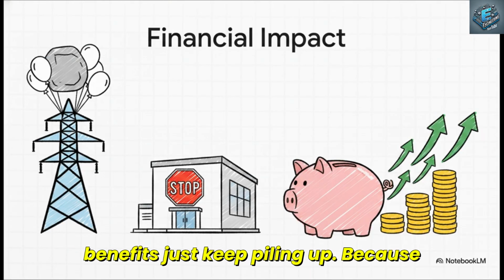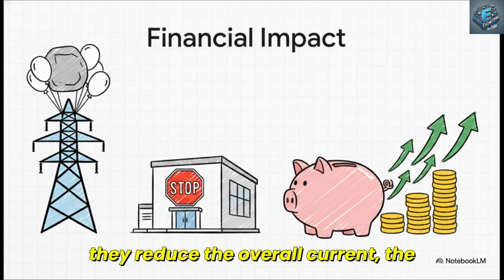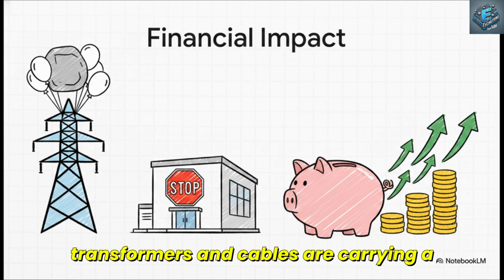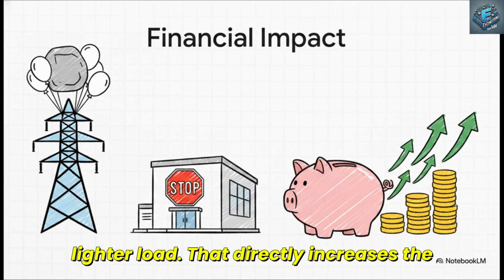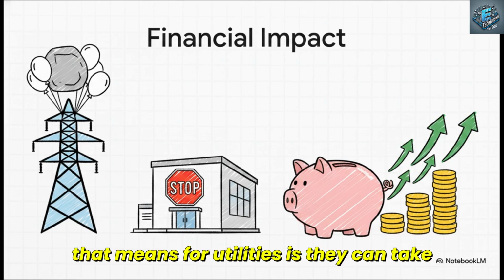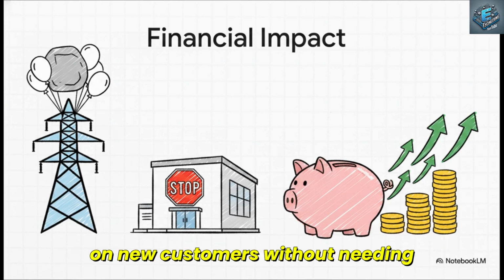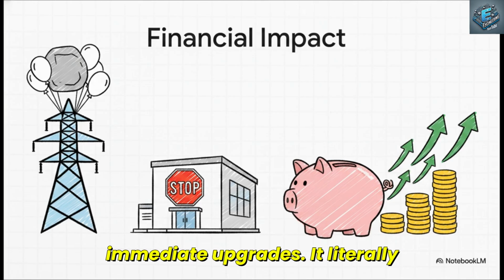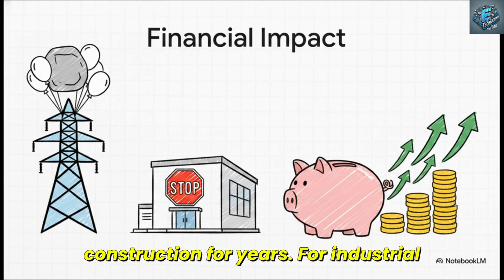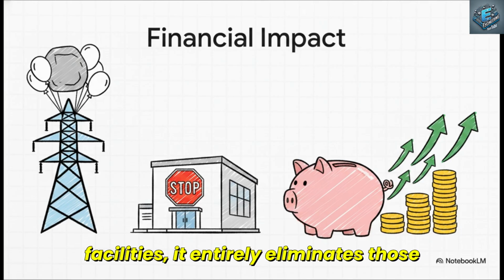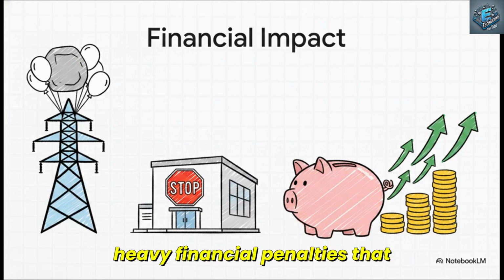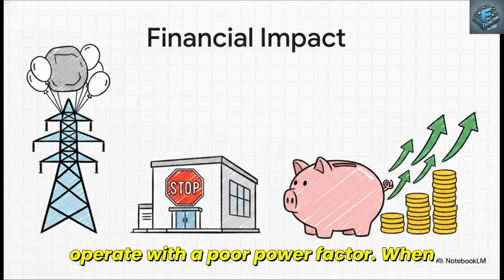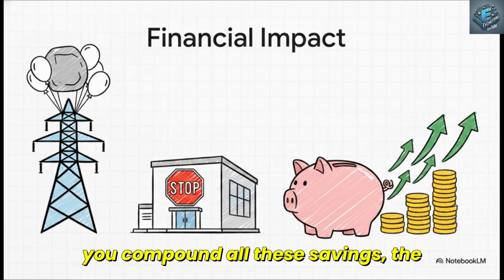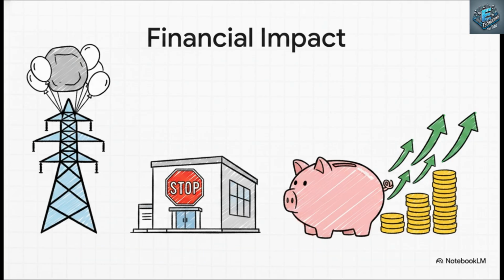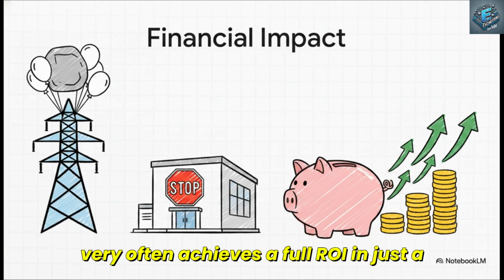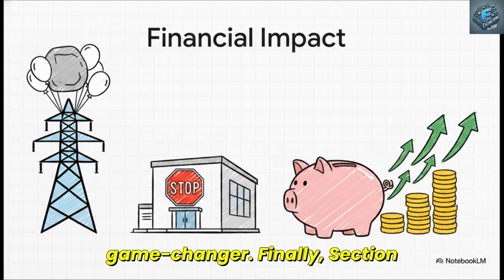And the bottom line benefits just keep piling up. Because they reduce the overall current, the transformers and cables are carrying a lighter load. That directly increases the capacity of the existing equipment. What that means for utilities is they can take on new customers without needing immediate upgrades. It literally postpones expensive new substation construction for years. For industrial facilities, it entirely eliminates those heavy financial penalties that electricity providers charge if you operate with a poor power factor. When you compound all these savings, the initial investment in a capacitor bank very often achieves a full ROI in just a few short years. It is a total game changer.